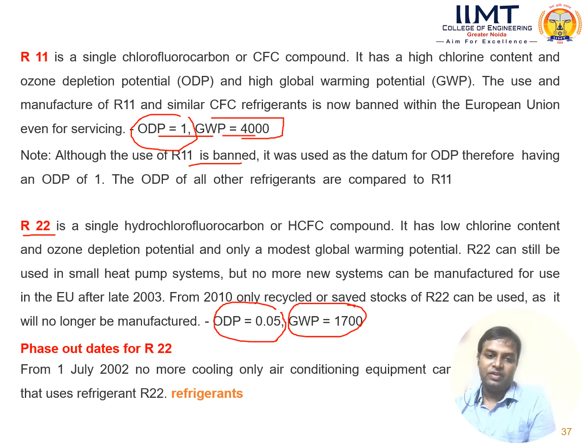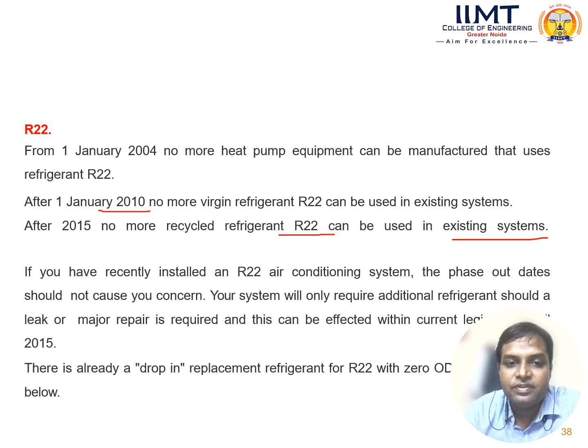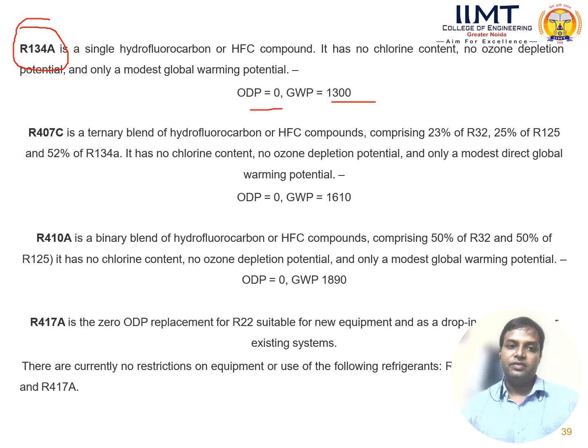Here you can see that after January 2000, no more virgin R12 refrigerant can be used in existing systems, and after 2004, no more recycled R12 refrigerant can be used in existing systems. There are some replacement refrigerants for R12 that we will see in future. Also, most of our refrigeration uses this refrigerant, which has ODP 0 and global warming potential 1300. Similarly, R404A has zero ozone depletion potential, but a global warming potential of 1600.